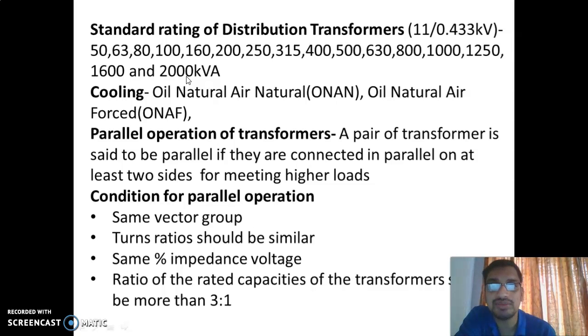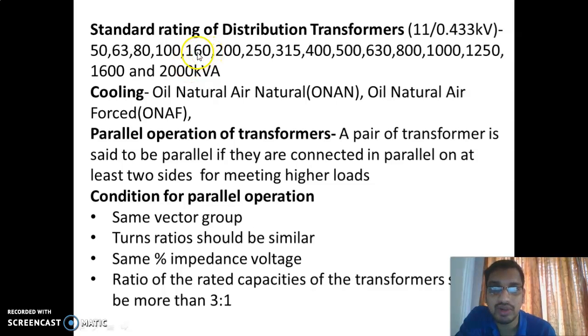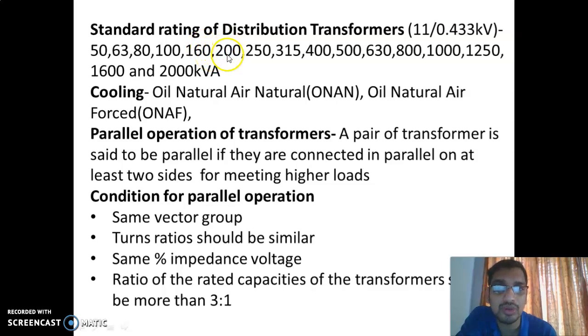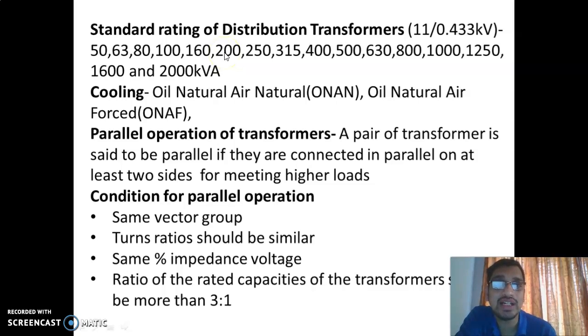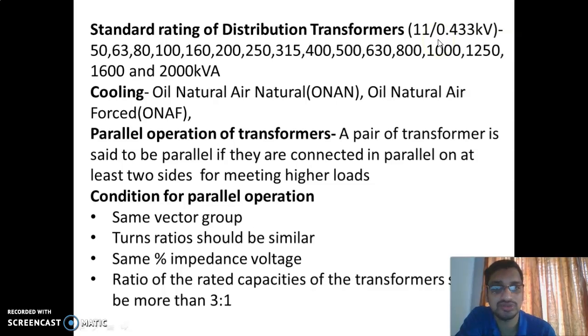For example, if the maximum demand is 180 kVA, we have a 160 kVA transformer size and the next is 200 kVA, so for 180 kVA you should install a minimum 200 kVA transformer. If the capacity is 210 kVA, you should install a 250 kVA 11 kV / 0.433 kV transformer. That is the selection of transformer capacity.